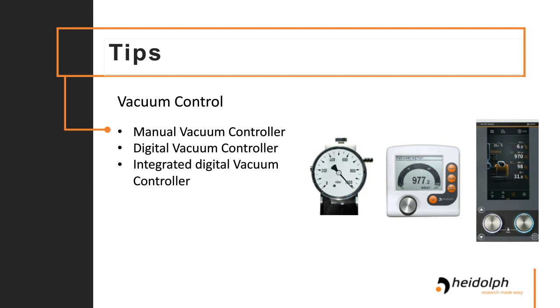And if you have the choice, I would always recommend going for the integrated digital vacuum controller, because in the evaporation process you have different parameters that all have a relation to each other, especially the vacuum and the temperature. So it makes absolute sense to have that on one control unit. It also makes it easy for you to save specific favorites, like if you evaporate ethanol very frequently, you can figure out once which parameters you need, save them, and start with one button only. This is a big step forward regarding comfortable usage of the rotary evaporator, and also regarding efficiency in the lab.